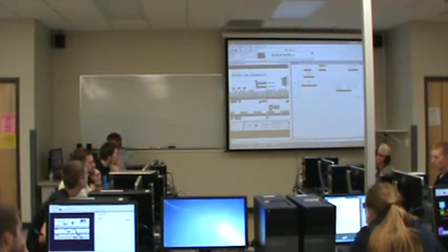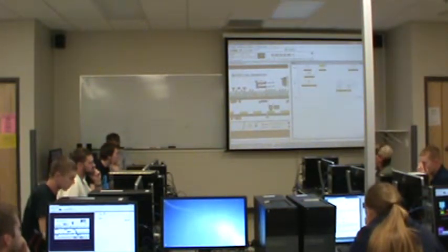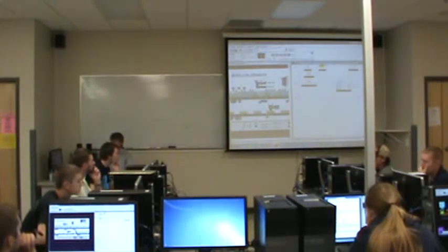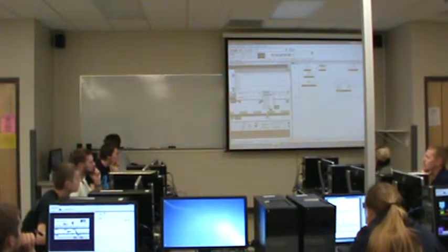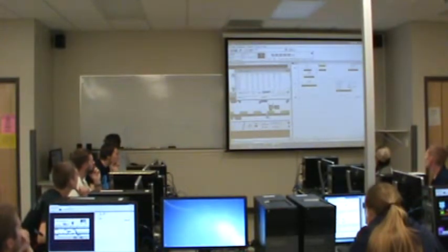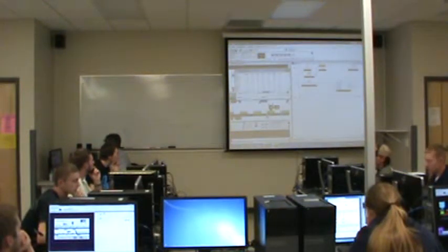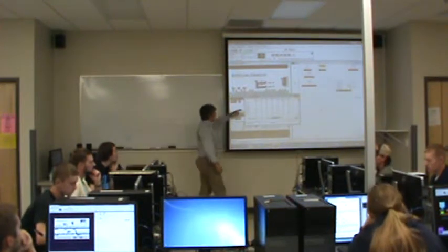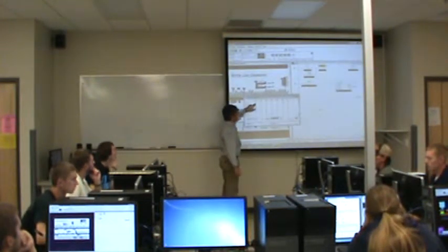I don't have to put that in. If I don't put that in, the counter will go up all the way to 65535 before it starts back over at 0. Let me show you why. If you look in memory at the counters file, you can actually see all the data associated with this counter. This is counter 0. Let me pull it down where I can reach it. This is counter 0. Here's the count up bit for that.